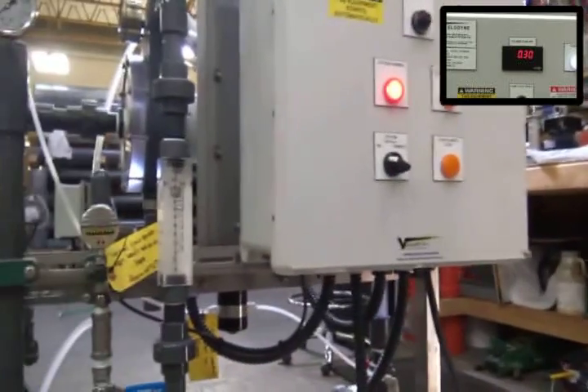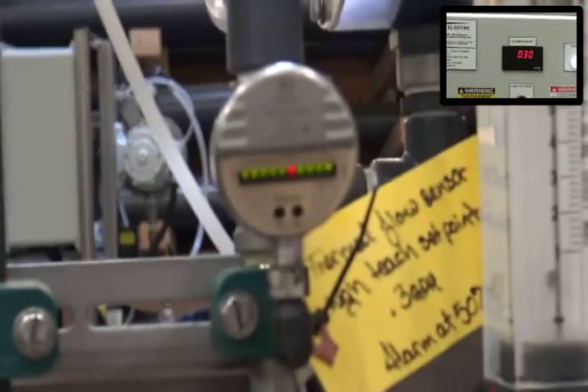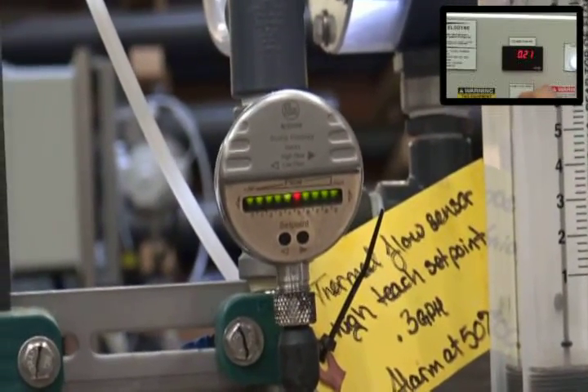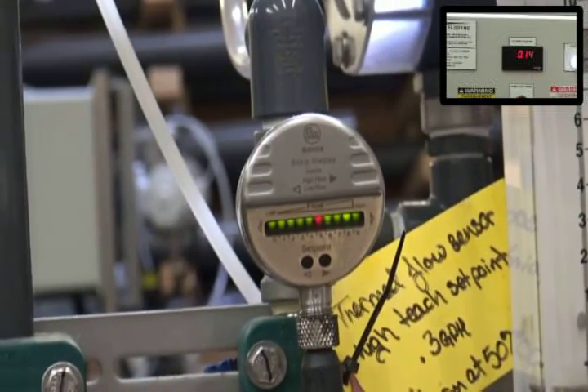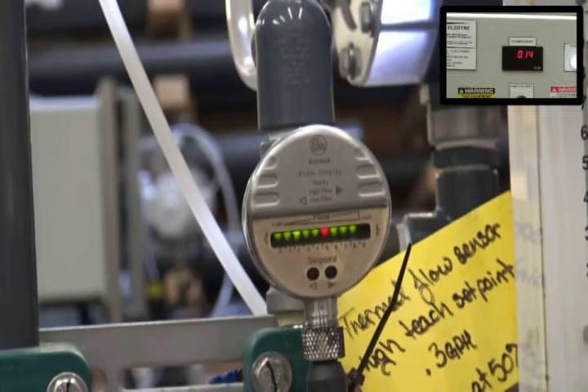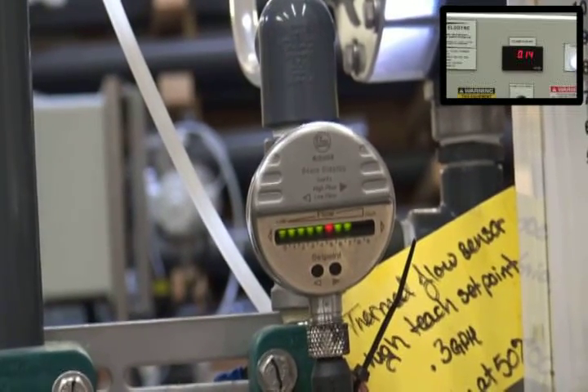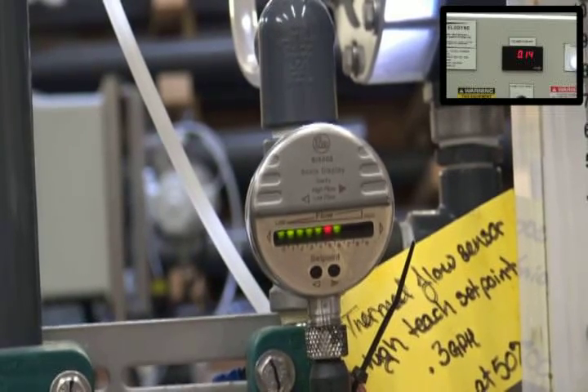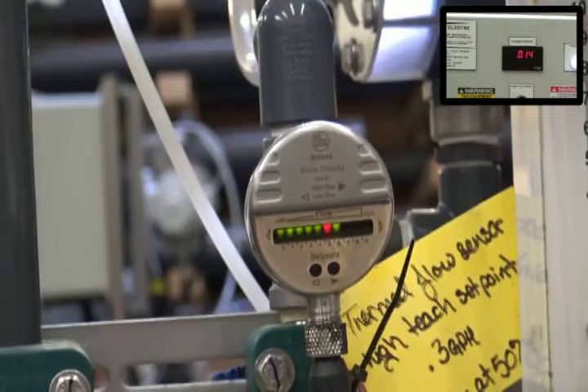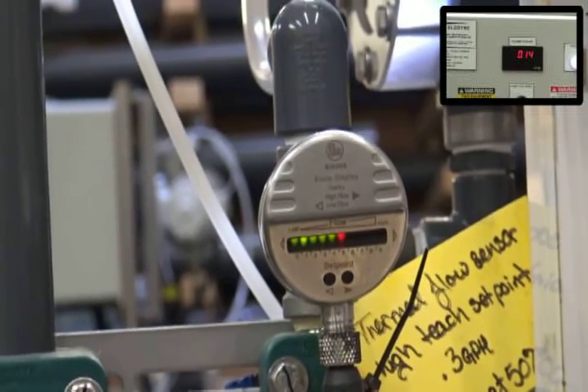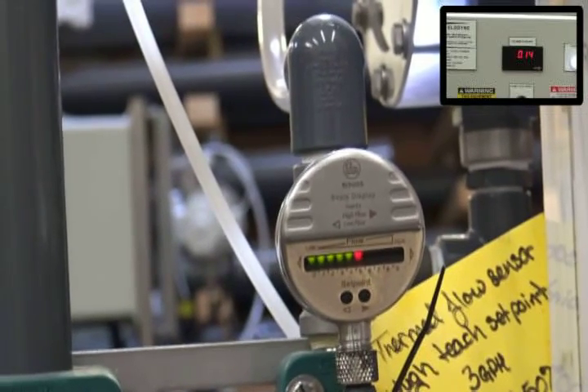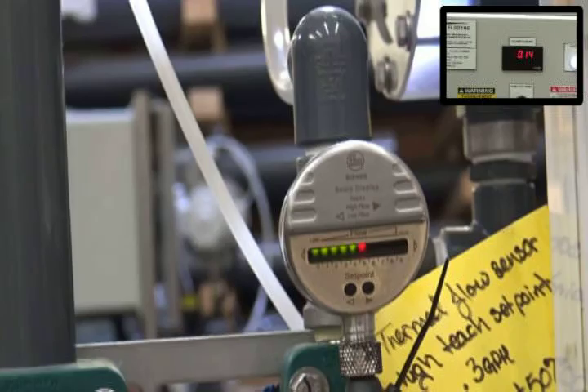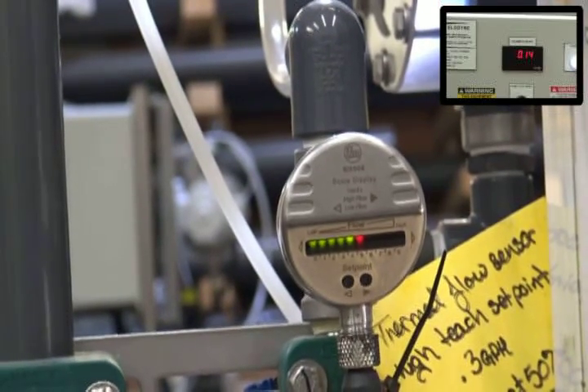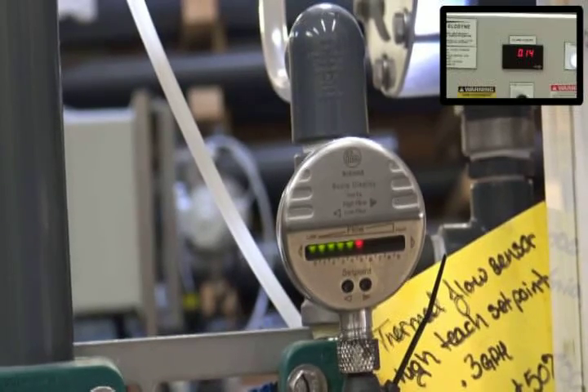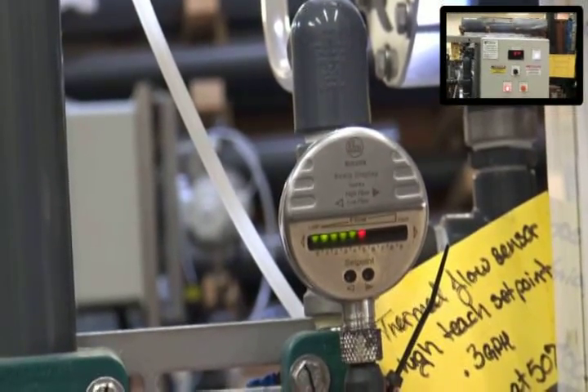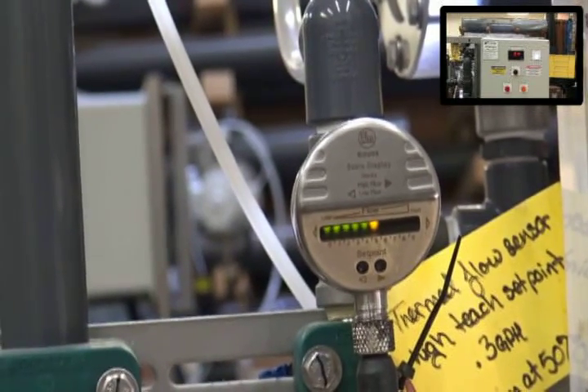and if you really want to, you can go ahead and test the fact that it actually works and turn the dial back down to where you know it's going to alarm out, and give it a second or two, let those lights go down. And if we did everything properly and everything is wired properly, we should get an alarm. And it just shut off.